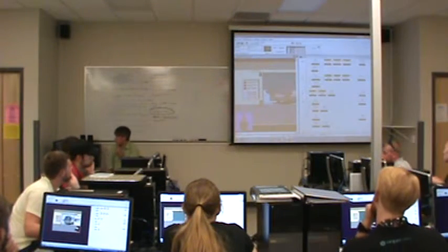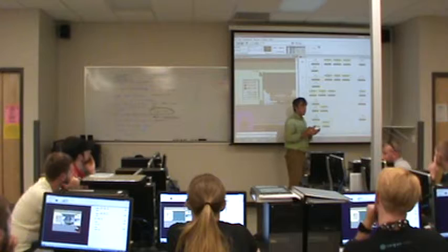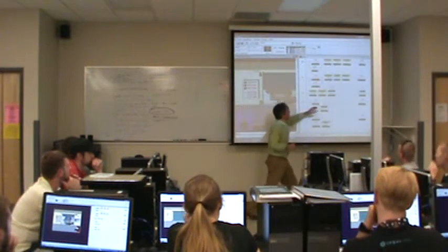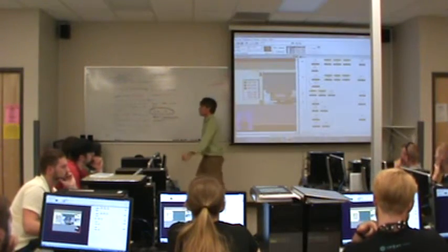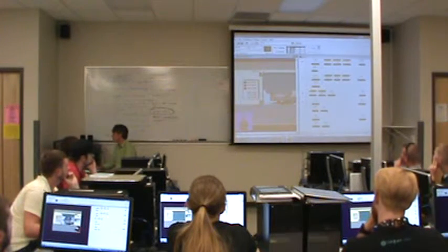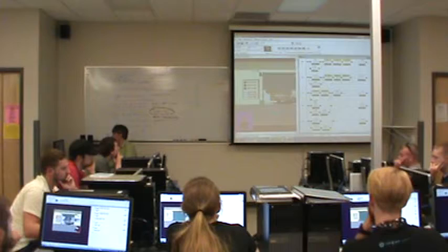Now the ajar lamp, I think what I want to make it do is when the door is in motion but is ajar, that's when it should flash. I don't want it to flash all the time. If the door stops like it does right now, I want the ajar lamp to be on solid. So I'll have to pull this out. So I'm going to OR around this just like I did before. But the conditions for the ajar lamp flashing are slightly different. So let's OR around the upper and lower limit switch, which together indicate that the door is between the upper and lower limit. I'll put the flash down here.